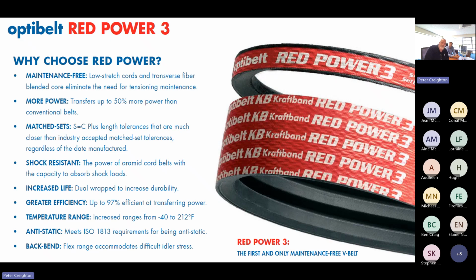And if you use that in conjunction with Red Power belts, and people say, why choose a Red Power belt? A Red Power belt is a maintenance-free, non-stretch belt. So it means that within the 3 years lifetime of a belt, when it's set up correctly, there is no maintenance required. So you never have to retension the belt, and by not retensioning the belt, you transmit more of your kilowatt power. To put it in context, the standard belt needs to be tensioned 10 times within 3 years. If it's not tensioned 10 times within 3 years, it will transmit maybe 78 to 80% of your kilowatt power. That means you're losing 20% of the kilowatt power of the motor due to slippage, and the slippage between the belts and the pulleys is what causes that.